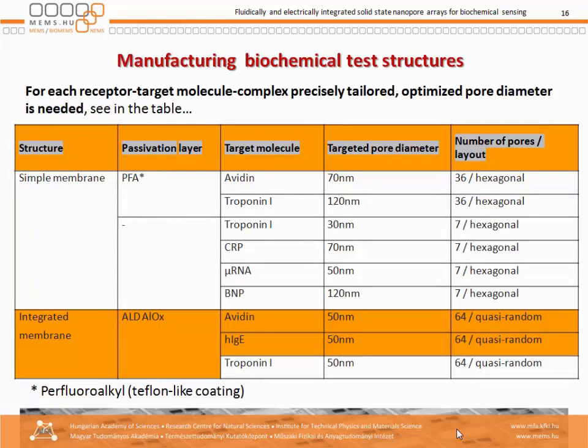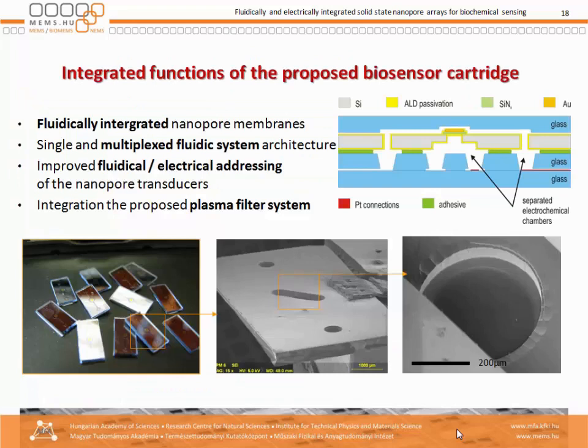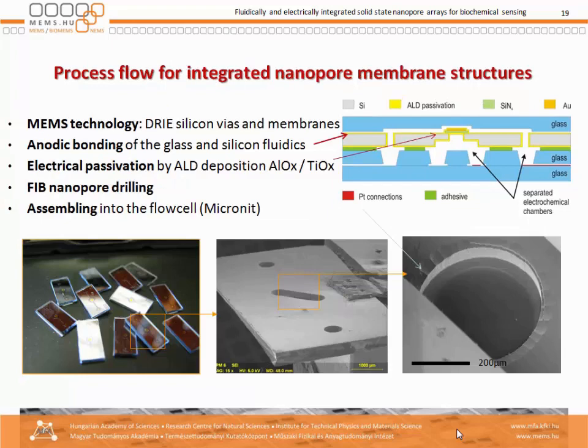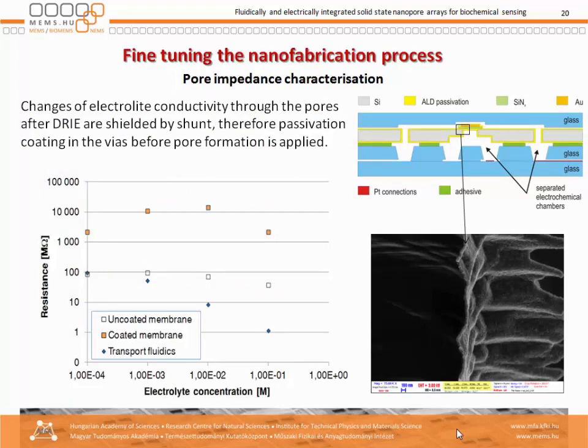These are some target molecules with their specific diameters listed, showing that we need an optimized situation for different target molecules. Finally, the whole nanopore has to be integrated into a microfluidic device because we want blood to enter and the liquid to pass through the nanopore. This is a complex glass-silicon-bonded structure with two separated compartments — the entrance for the upper compartment and the bottom — and the microfluidics is done in silicon.